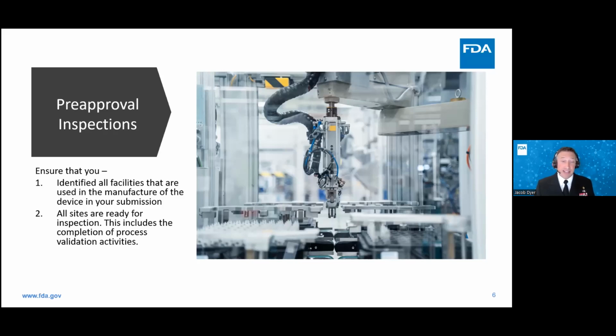It's also possible that the determination of a pre-approval inspection is not required. Sometimes if your facility has already been inspected and determined to be acceptable, and the benefit-risk-based approach determines that a pre-approval inspection is not required, you may not need one, but that will be on a case-by-case basis. The key is to ensure you have identified all facilities used in the manufacture of the device in your submission, and that all these sites are also ready for the inspection.